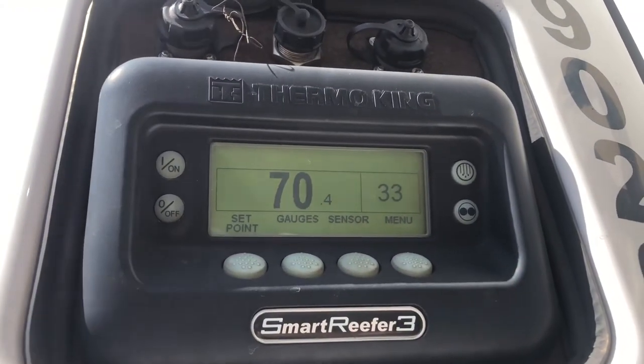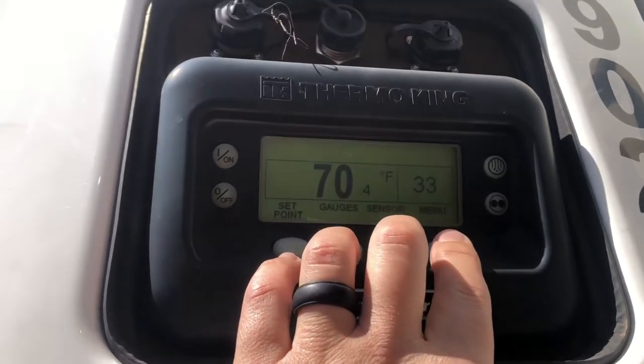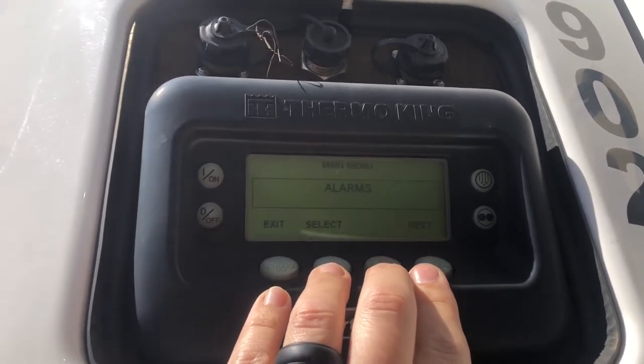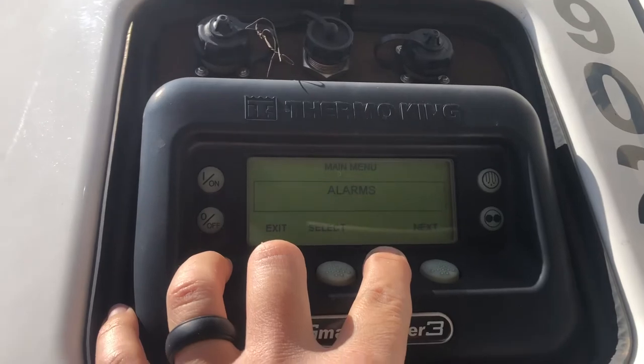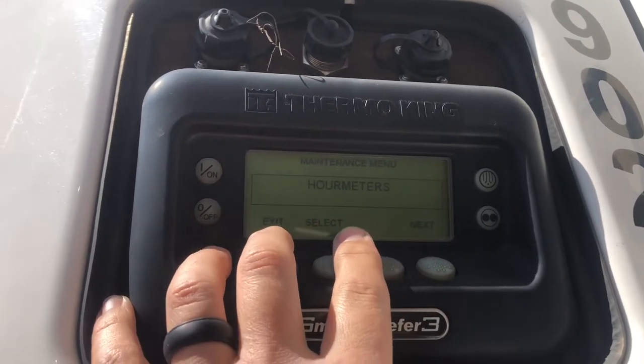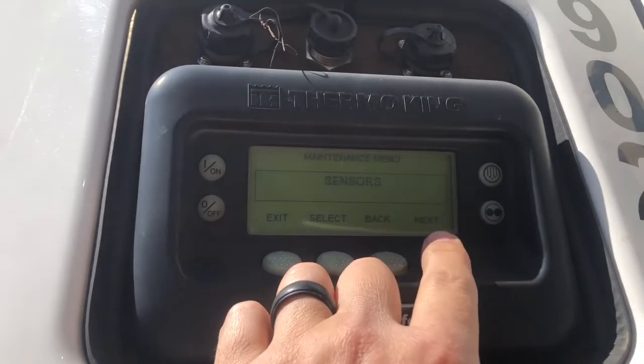This is how to get into Thermo King guarded access. Go into the menu, hold down the blank key and the exit key for about three to four seconds, and then it brings you into the maintenance menu.